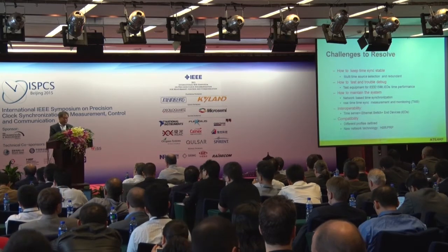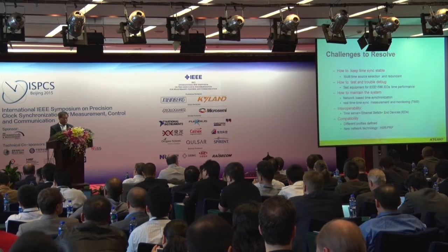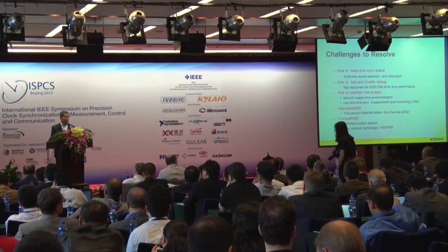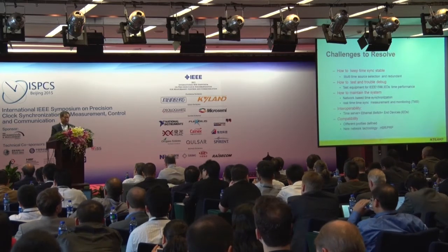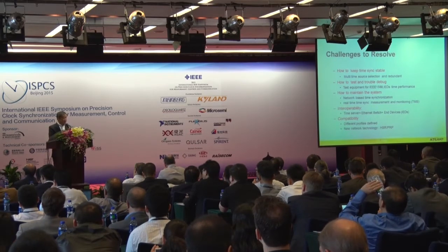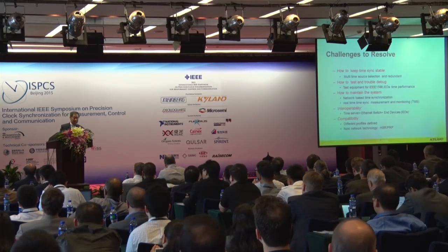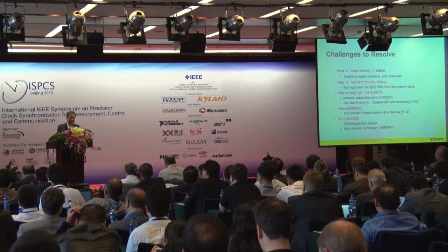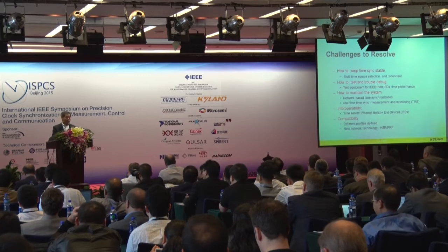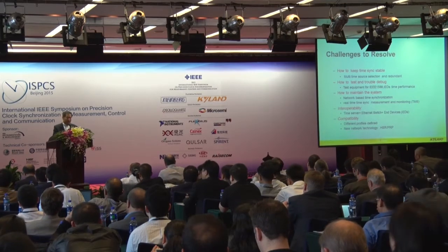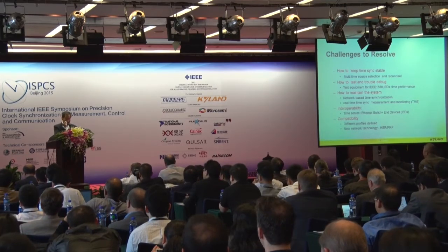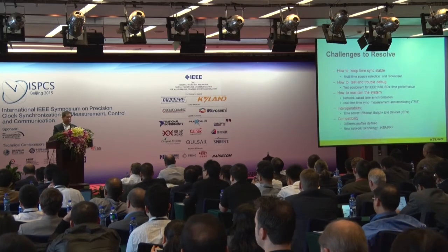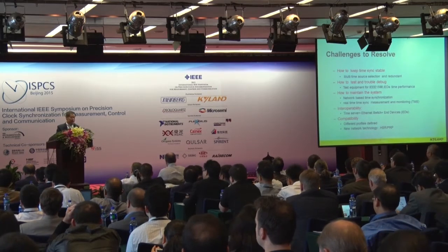Also, in the substation, we have to monitor the time difference in real time. Just like I mentioned for merging units, if some merging units lose the time synchronization, maybe big trouble. So we monitor this time synchronization performance in real time. We call it TMS.